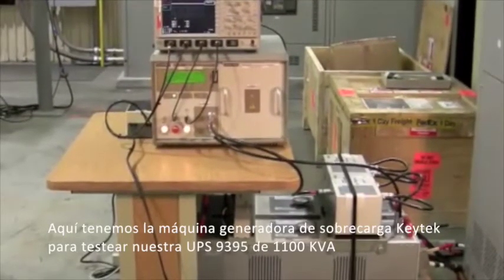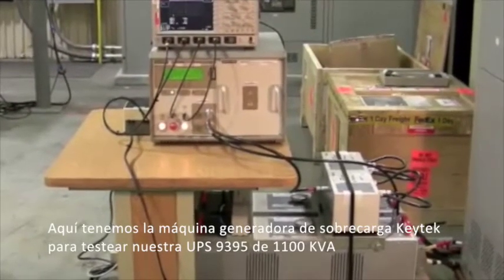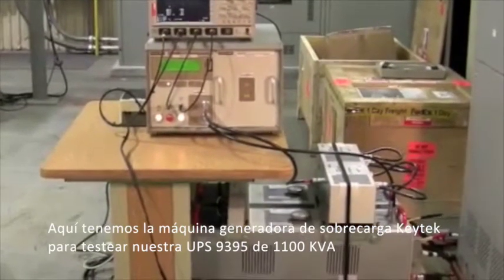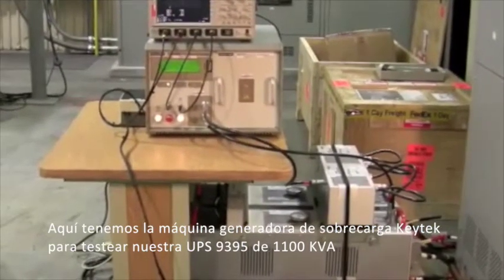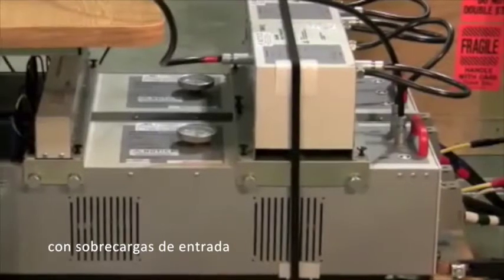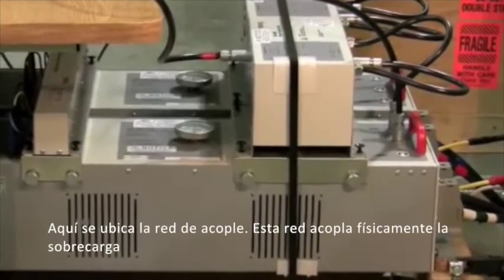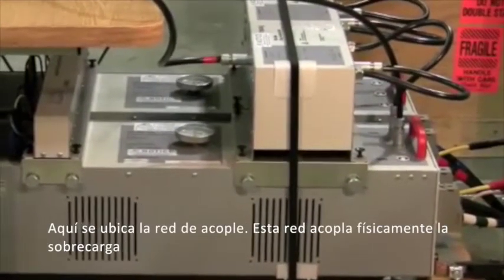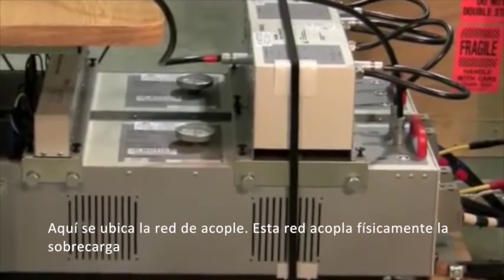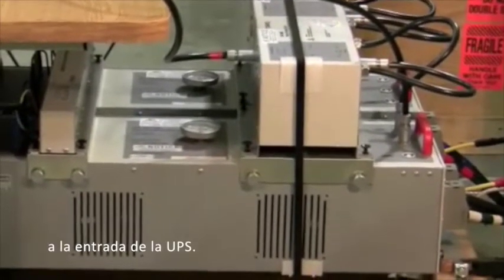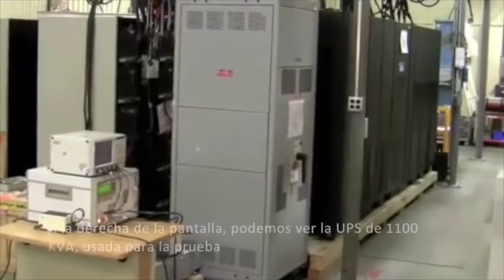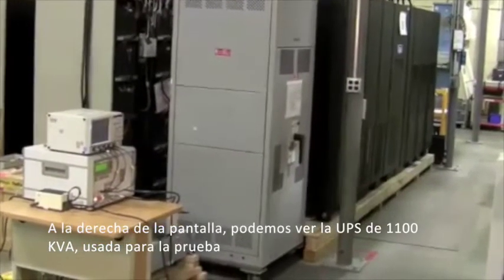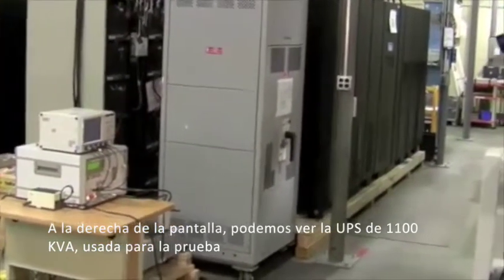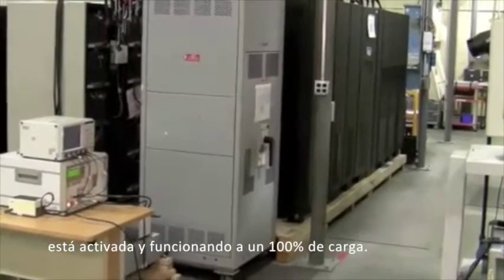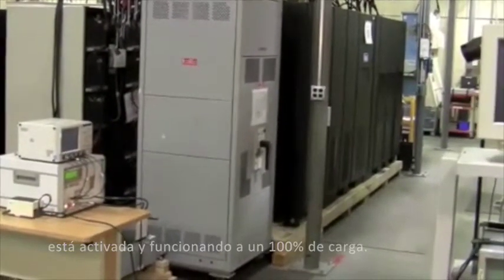Here we have the Keytek surge generator machine that we're going to use to test our 1100 kVA 9395 UPS for input surges. Underneath the Keytek machine, we see the coupling network. This network physically couples the surge onto the input voltage bus bars of the UPS. In the right-hand half of the screen, we can actually see the 1100 kVA UPS we're using for the test. It is running and operating at 100% load.